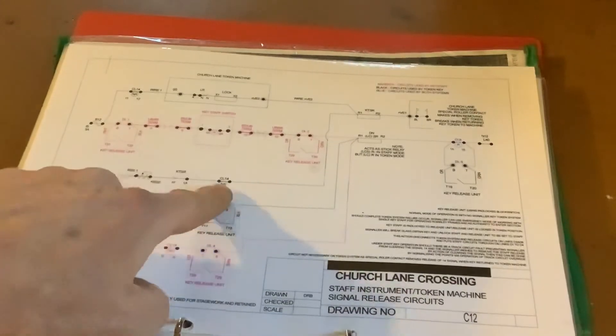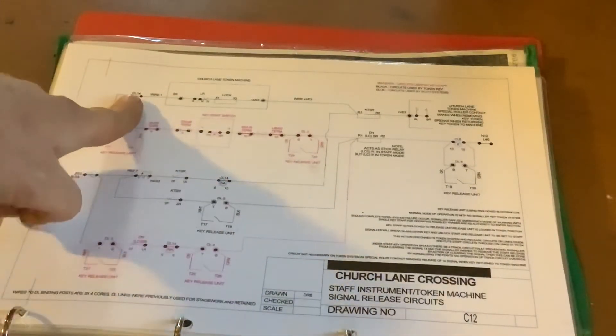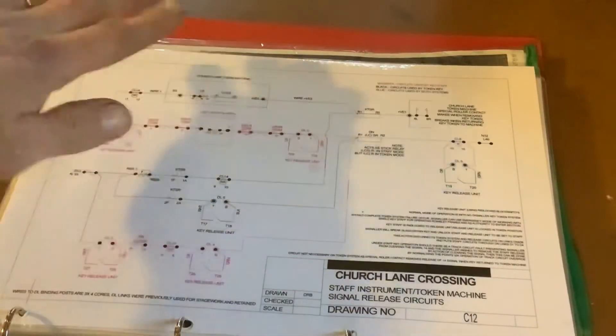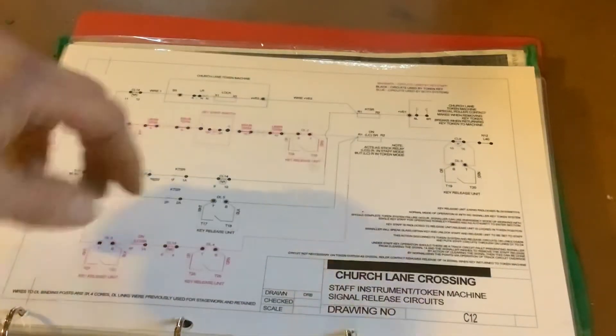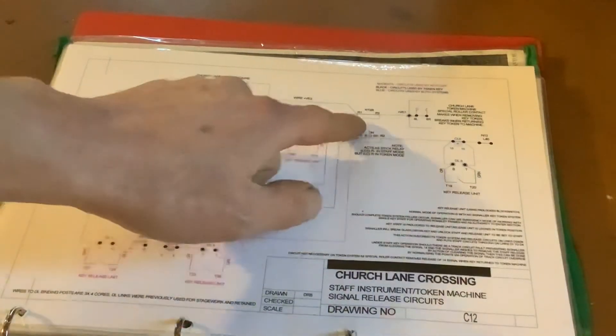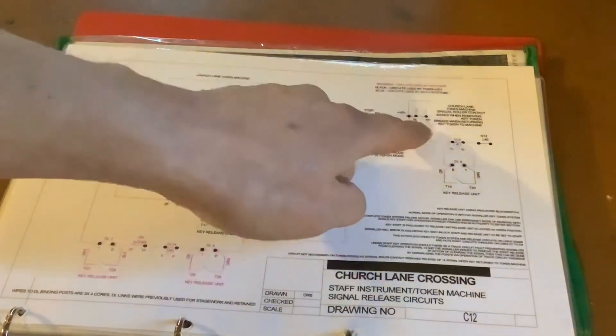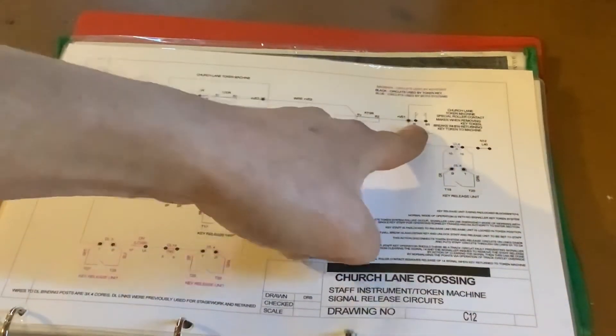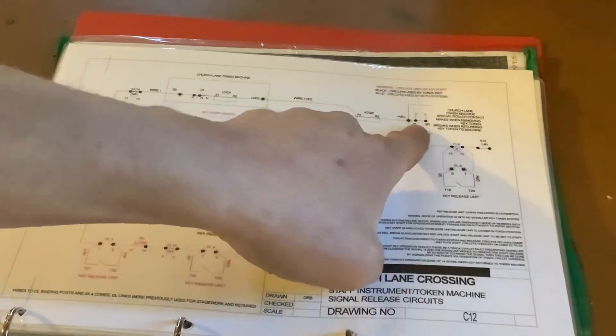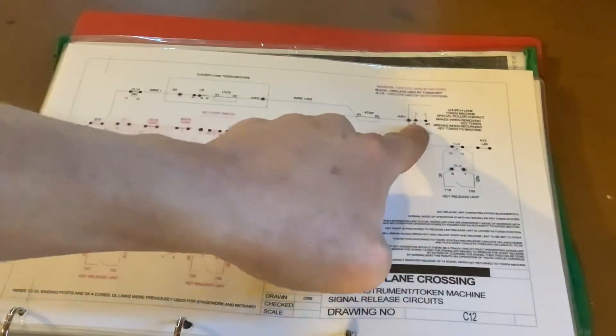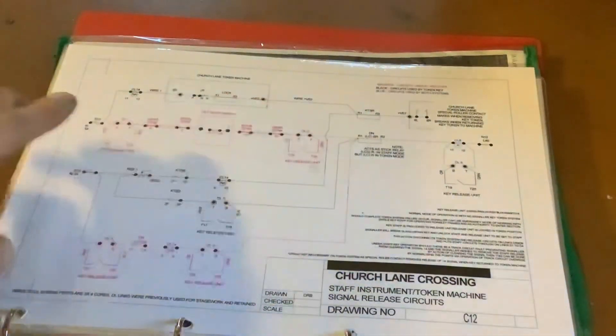However, when we clear our starting signal, not only do we break this path and also our original path, again we've lost all paths that can clear this signal again. But at the same time, as we take our key out, this has stayed energized. But as soon as we go and put our key back in to cancel it, it again breaks any possible feed path to get to that key token stick relay.